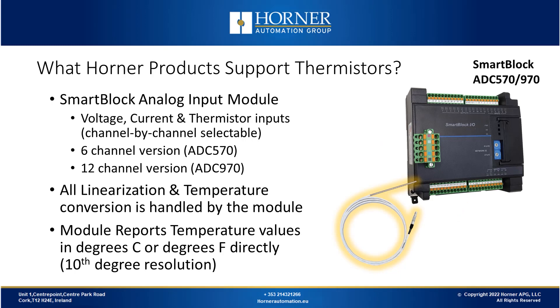Now we'll look at specific Horner products which support thermistors. Starting with the smart block analog input modules, the ADC570 and ADC970 — one is 6 channel and the other is 12 channel, but they have the same specifications. They both support voltage, current, or thermistor as inputs on each channel, selectable channel by channel, and the module handles all the linearization and conversion to temperature on board. Temperature values reported by the module are in degrees Celsius or degrees Fahrenheit, reported in tenth-degree increments.